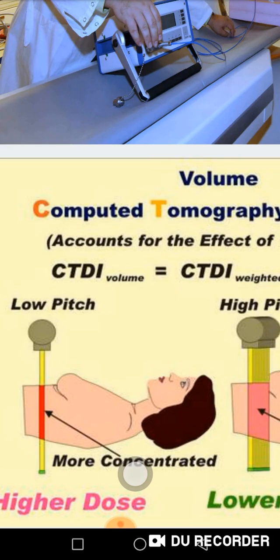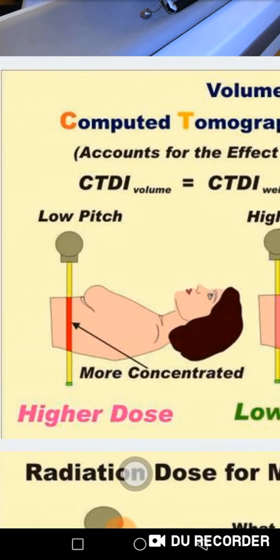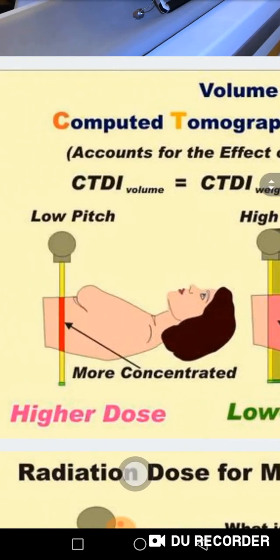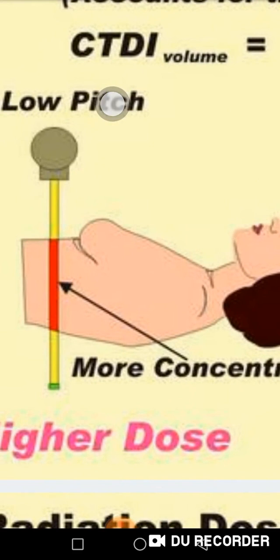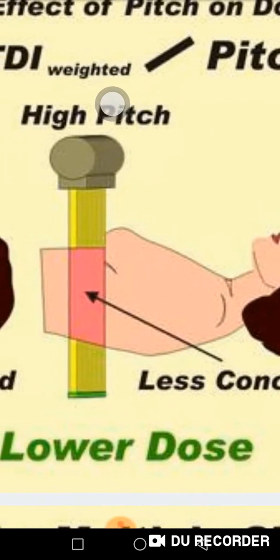If I include the pitch in the equation, I divide the weighted CTDI by the pitch factor, giving me the CTDI volume. The CTDI volume is a very important term you will see on any CT scanner. With low pitch — minimal table movement — the dose is more concentrated and higher. With high pitch, the dose is less concentrated and lower. The pitch factor is very important as it affects patient dose.